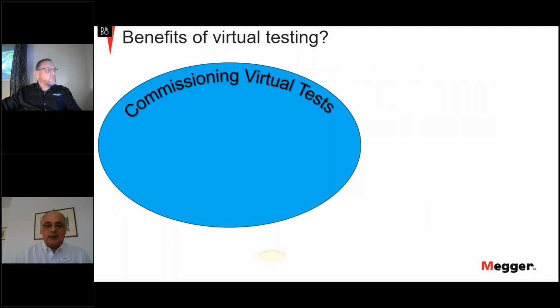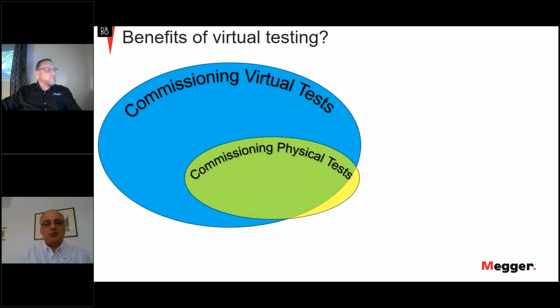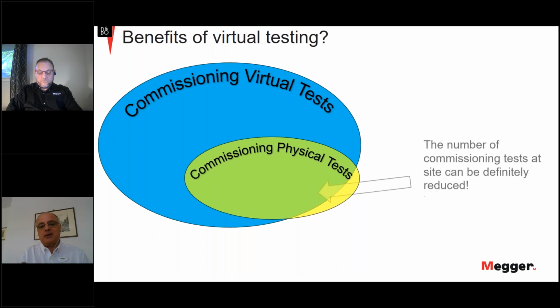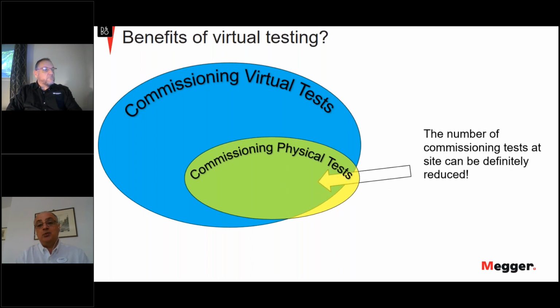Then at the end, what does it mean? The vision is a commissioning virtual test, which we do in the virtual world. Then a subset of them can be the tests I do physically in the substation, because the contact, the GOOSE method, must be tested to the breaker and to other relays there. But they are limited.